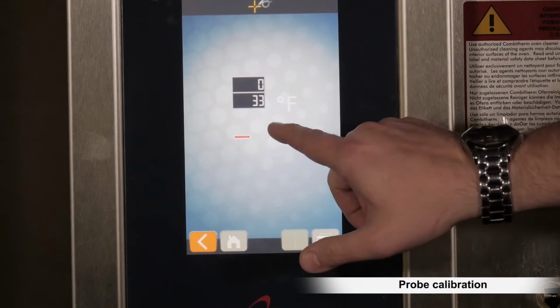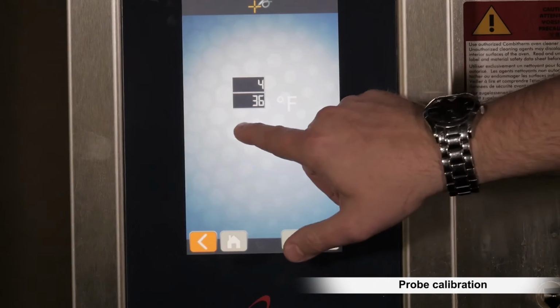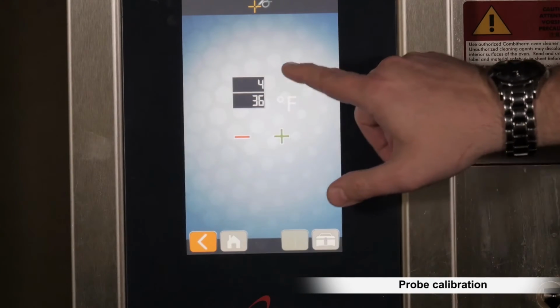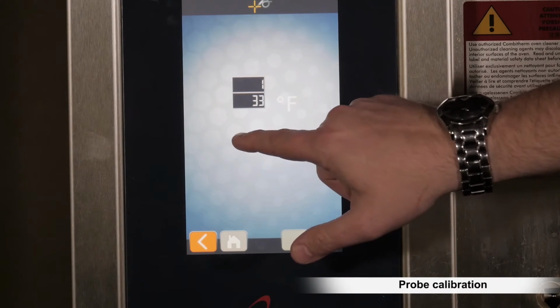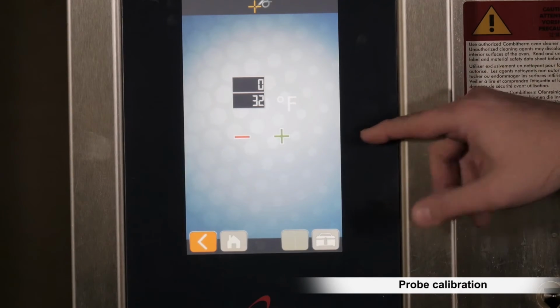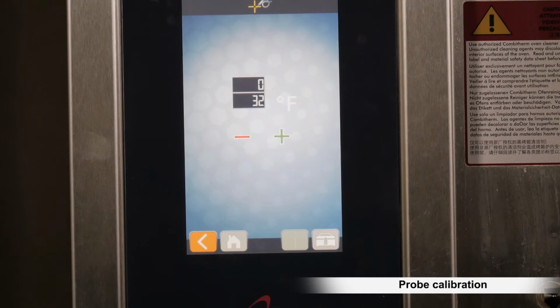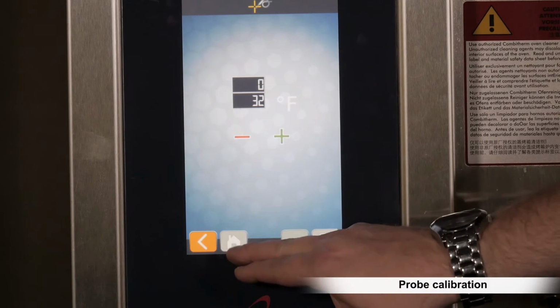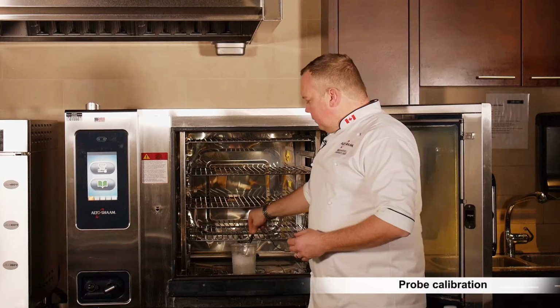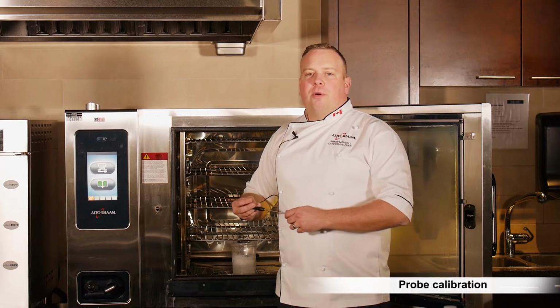Should I need to change the calibration, I could plus or minus this setting to reach 32 degrees. Right now this probe is calibrated perfectly, and I can go back to cooking. And that's how you calibrate the probe on your Alto-Shaam CTP oven.